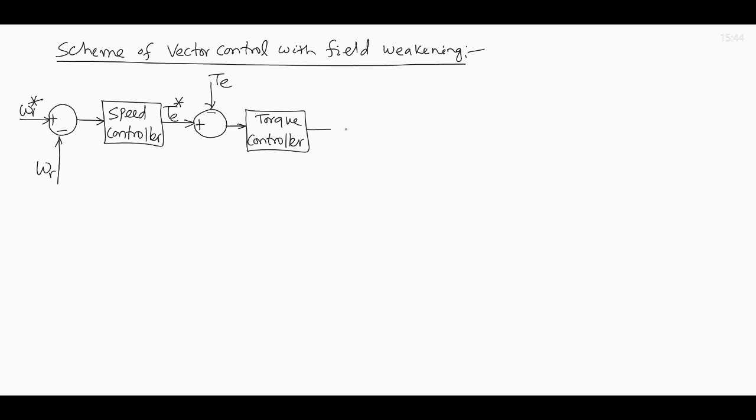And torque controller output has to generate the current command IQS star according to the expression, the square root of the permissible stator current IS hat square minus demagnetizing current IDS square, and this generates the plus or minus IQS star, plus for motoring operation, minus for generating operation.